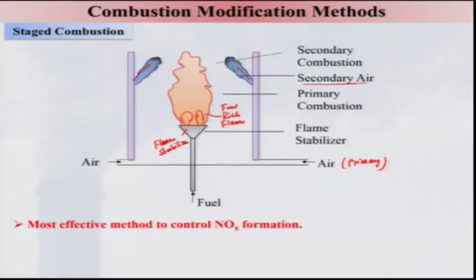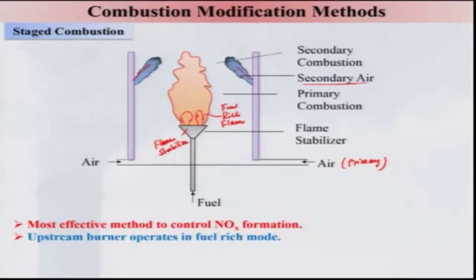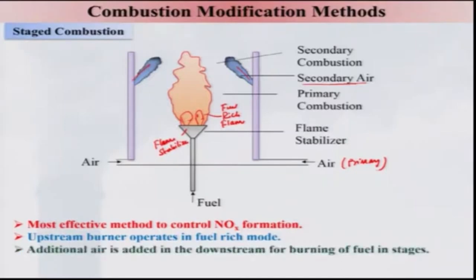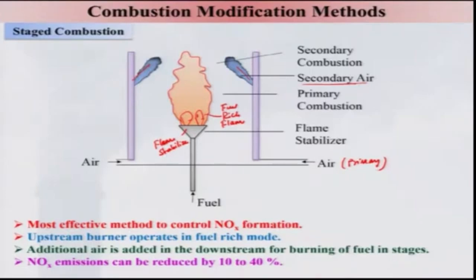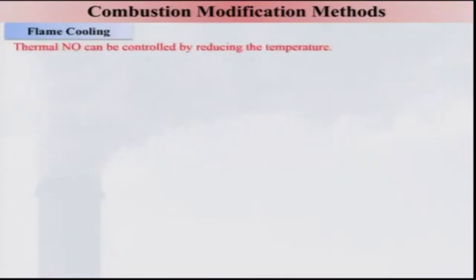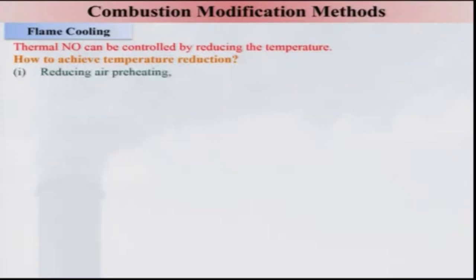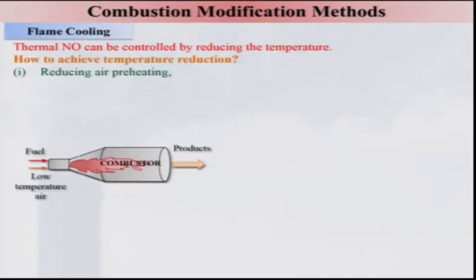This is the most effective method to control NOX emission level: the upstream burner operates in fuel-rich mode and the downstream section operates under lean conditions. When additional air is added downstream, thermal NOX emission can be reduced by 10 to 40%. Regarding flame cooling, thermal NO can be controlled by reducing the temperature of the combustion gases — achieved, for example, by reducing the preheating of air entering the combustion chamber.